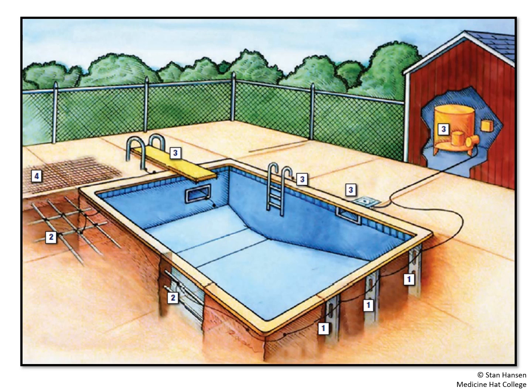Any permanent or in-ground pools must be grounded with a minimum of a number 6 copper conductor, and any other pools that we have, such as above ground pools, we'll use Table 16.